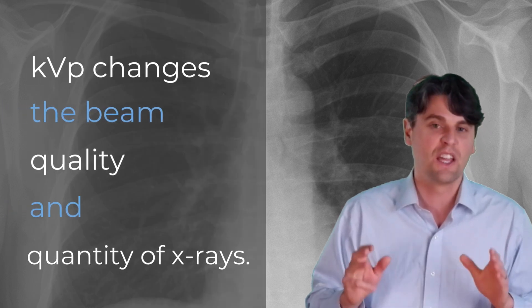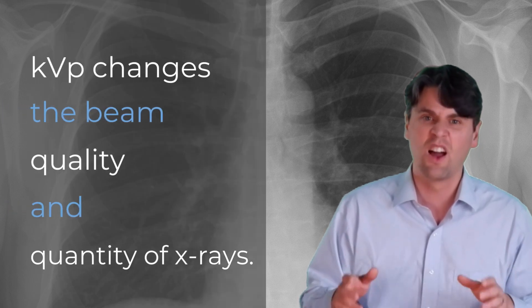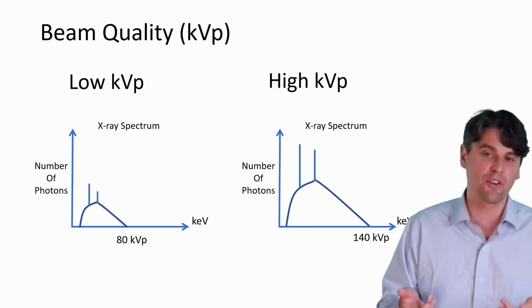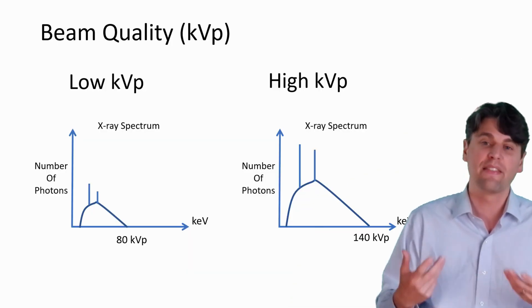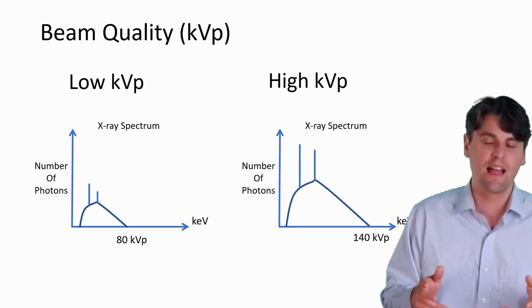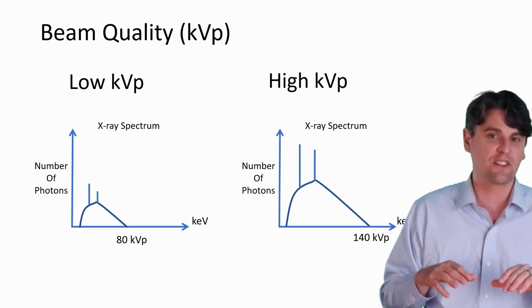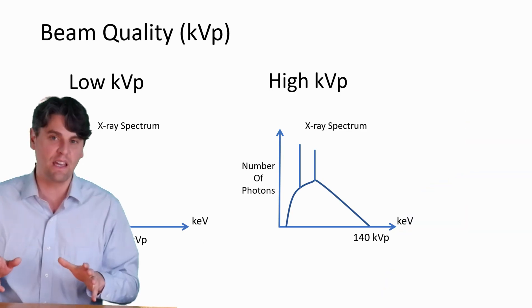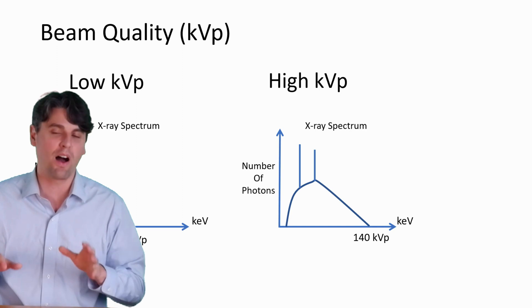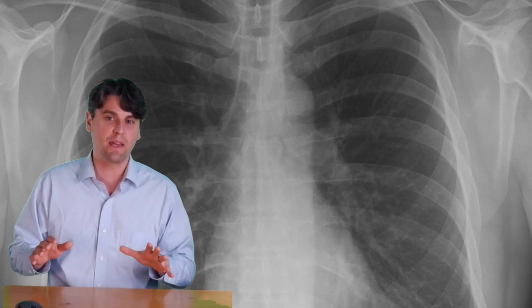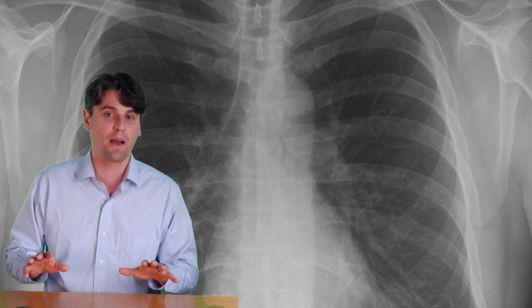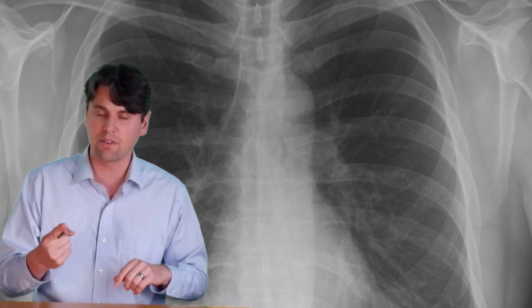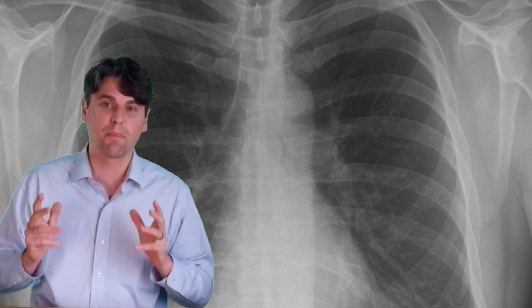And when you change KVP, you're changing both the quality and also the quantity. So the number of x-rays or the area under the curve in the x-ray spectrum, that's what we call the quantity or the number of x-rays. And the quality is actually the shape of the x-ray spectrum. Go to higher KVP, you're changing the shape of your x-ray spectrum. Change the KVP alone without changing any other parameters, you're actually going to end up with higher quantity of x-rays and also a different beam quality.